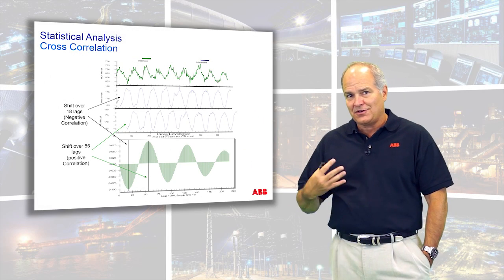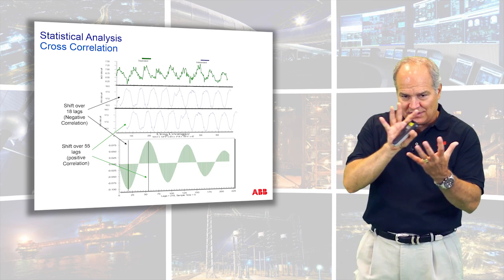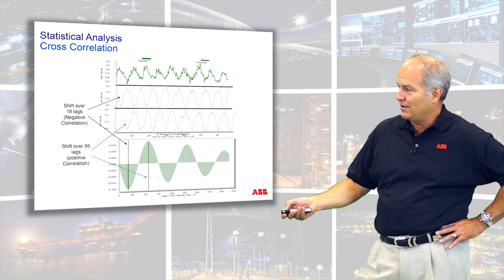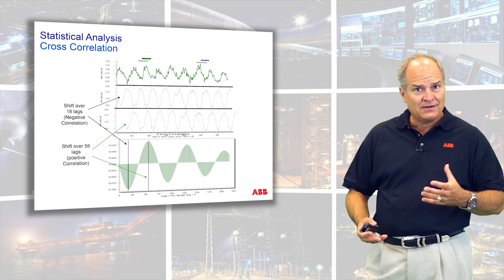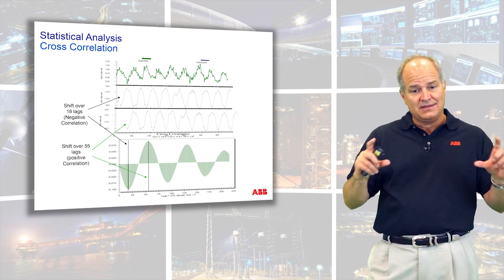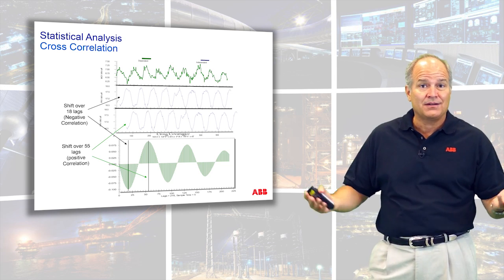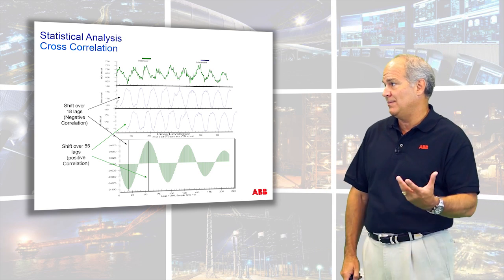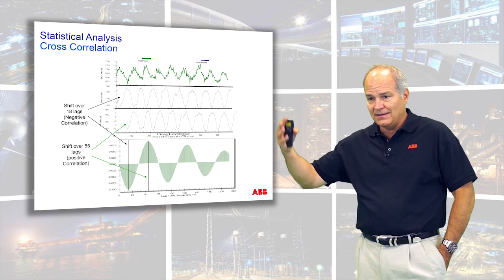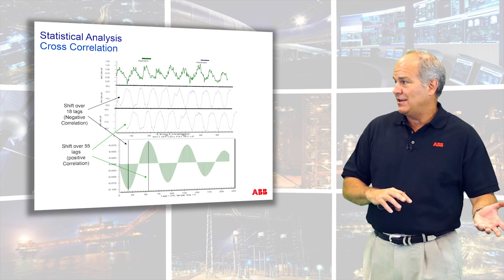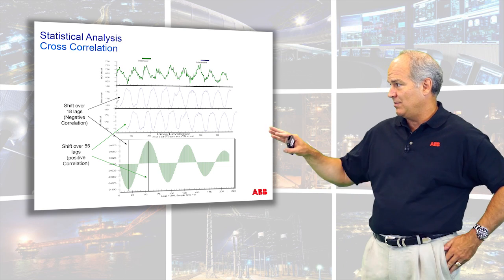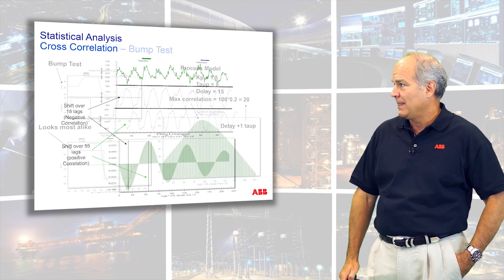So when you're looking at a cross correlation, you really need to actually see the signal shifted, and that's what we can do with this software. It allows you to see, is that really there? And then you're like, oh, well, if I go fix this parameter, then the other one will just get better. It's not a tuning issue. It could be at this loop, or it could be some disturbance, or in this particular one, they had changed the main valve, thrown in some default tuning, and it just was banging all over the place. So we fixed that, and the whole machine calmed down.